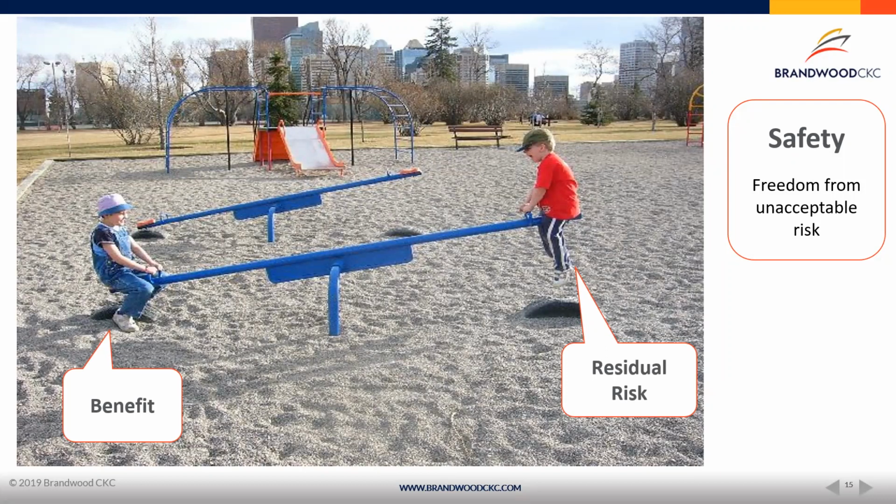And I don't think you would have a marketable medical device without your benefit outweighing your residual risk. So after all the controls are in place and you've identified what the residual risk is, you need to be able to say that the benefit outweighs that risk. That is the key fundamental principle for most regulators in the space. They want to see the establishment of a risk-benefit profile that is obvious to them, that it's more beneficial than creating risks.